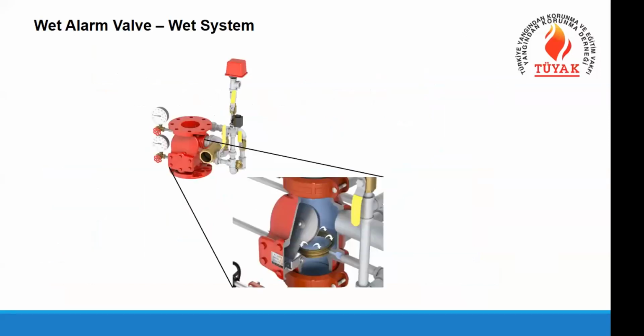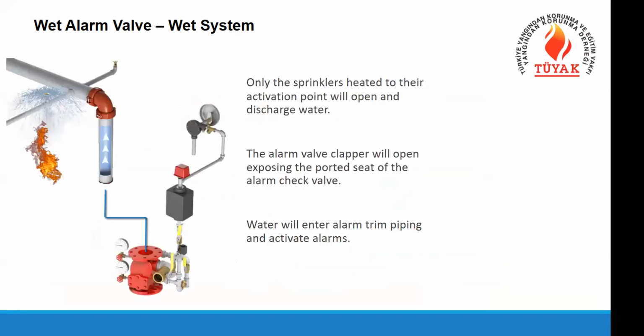So we use here wet alarm valves, which are called wet system alarm valves. And these valves are typically a check valve that allows the water to flow in a single direction, in the sprinkler direction. And the target of using this valve is to get an alarm from the system, and also to test the system before the fire happens. So we want the system to inform us when a fire happens or a sprinkler operates, and that should mechanically or electrically give an alarm to us. So let's see in an animation how this wet system valve works.